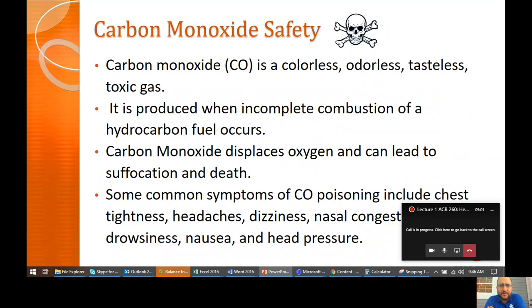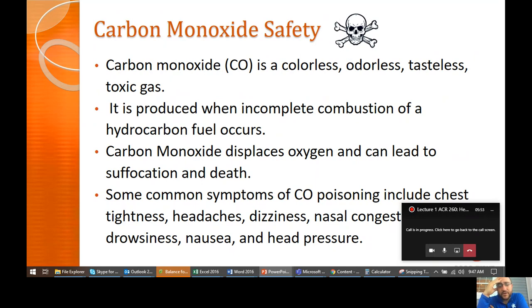Getting into gas — the biggest issues are fire and carbon monoxide, CO. Carbon monoxide is colorless, odorless, tasteless, and toxic. It's produced whenever we have incomplete combustion, usually when the incoming air supply doesn't have enough oxygen — it's oxygen starved, maybe it's blocked, or your heat exchanger is clogged. A furnace can produce carbon monoxide and still be safe as long as your exchanger and pipes are good and it's vented properly so it doesn't come back into the house. You've got to worry about your vent location and the state of your vent.